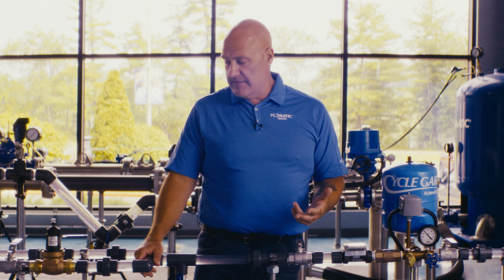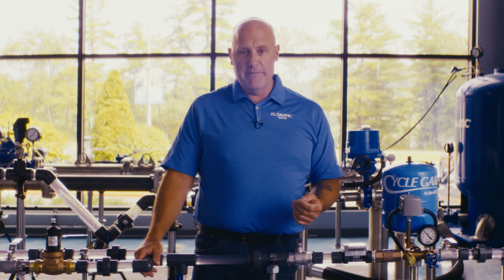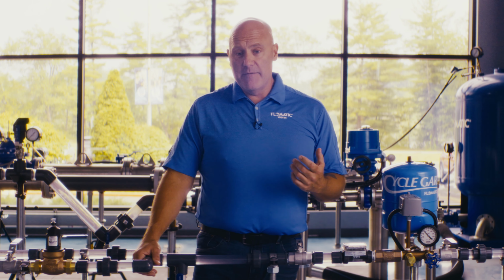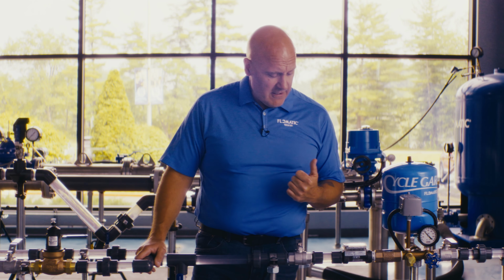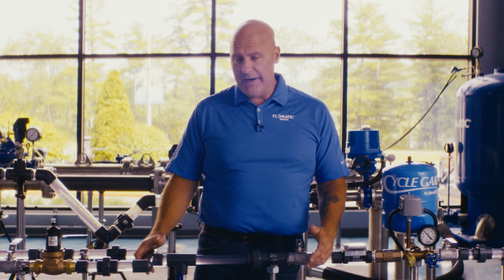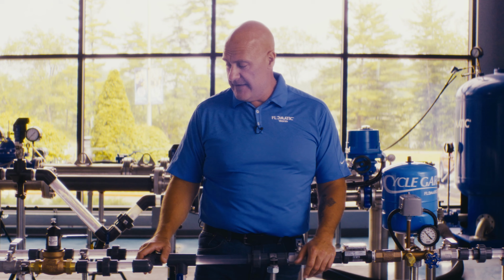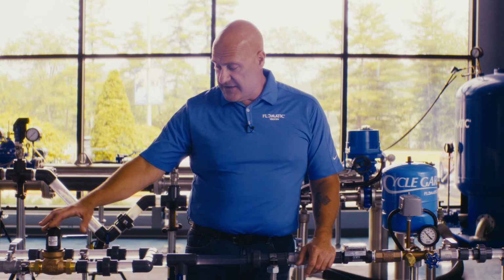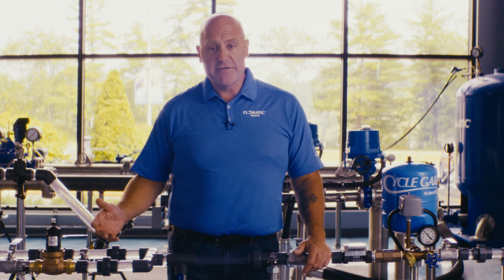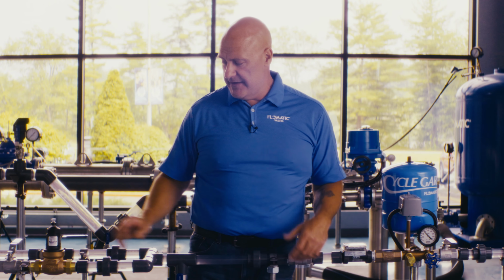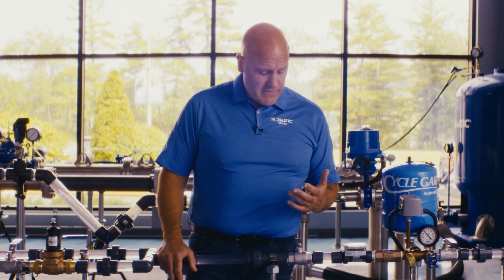Biggest culprits you might encounter would be mineral buildup, sand, maybe some pipe dope upon initial install. So it's very important to try to keep debris to a minimum. If there's a very sandy well, you may want to have a filter in line. And just use caution when installing them that we're not getting, again, pipe dope, thread sealant, something like that in the valve. If there is some problem, the adjustable units can be maintained. If the system is depressurized, they can be disassembled. The internal cartridge assemblies can be replaced, repaired, very easy to inspect. Reference your installation manual. There's directions there how these valves can be disassembled and reassembled. We offer repair parts. So very simple, very basic.